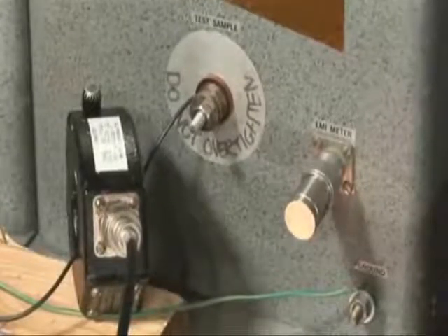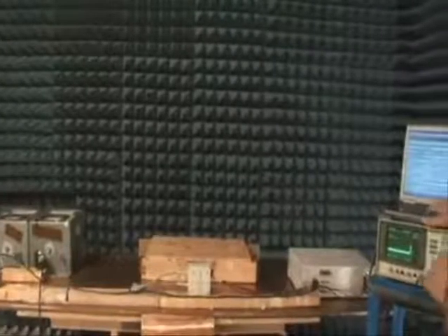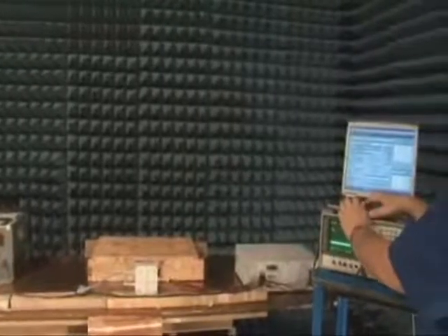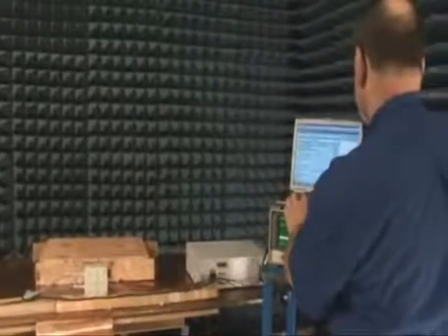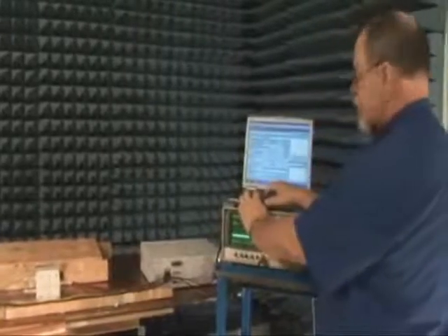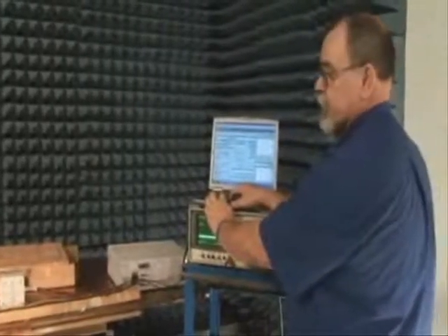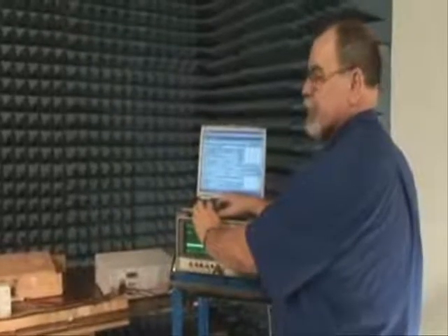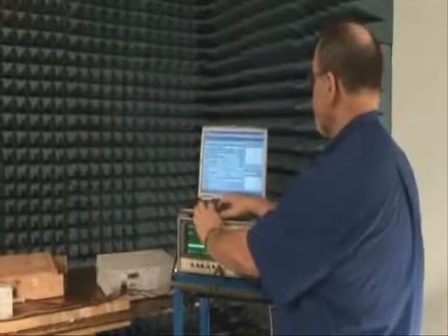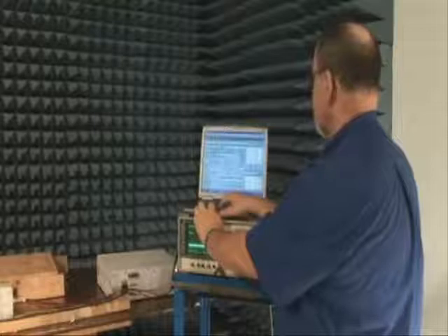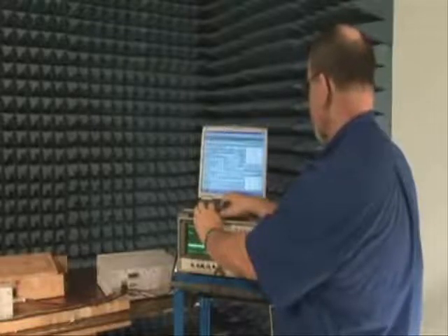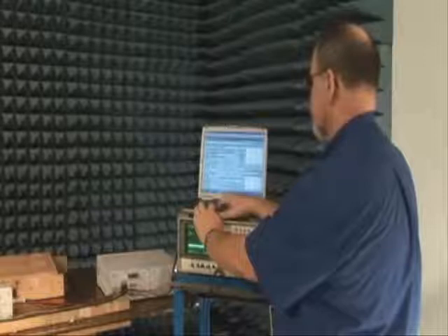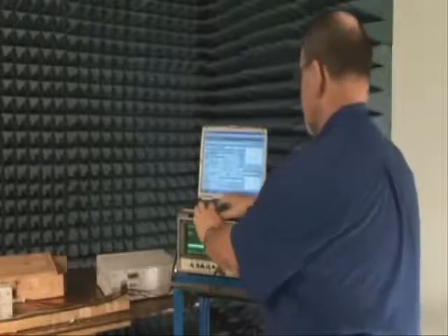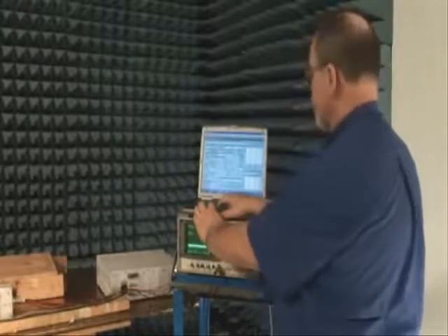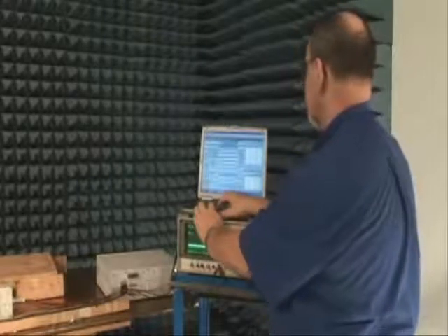So let's go back over and execute the software. I've selected the start frequency to be 120 hertz because the standard says we start the test at twice the power line frequency. Since this is a 60 hertz system, we start at 120 hertz and go to 10 kilohertz. Our software checks everything for the mil standard. We selected mil standard 461F. Well, actually our system says E, but this test is identical. So we basically just run the software.